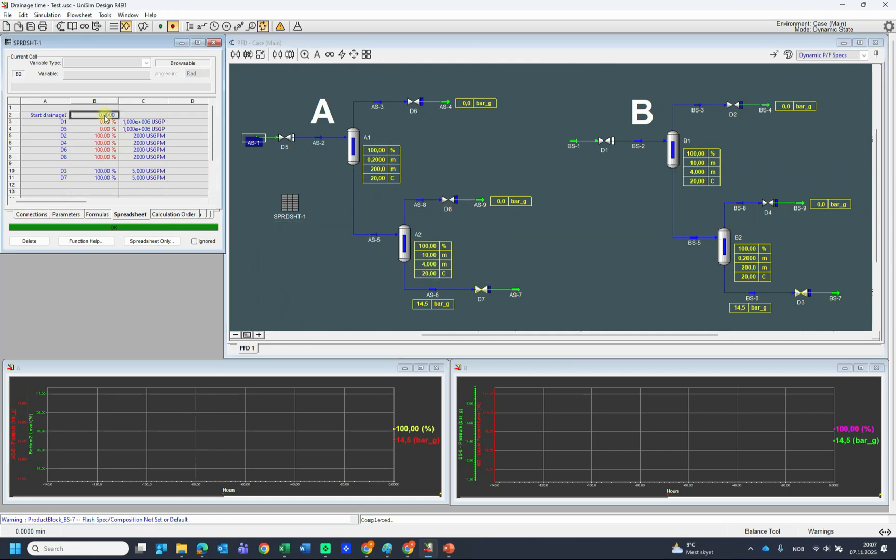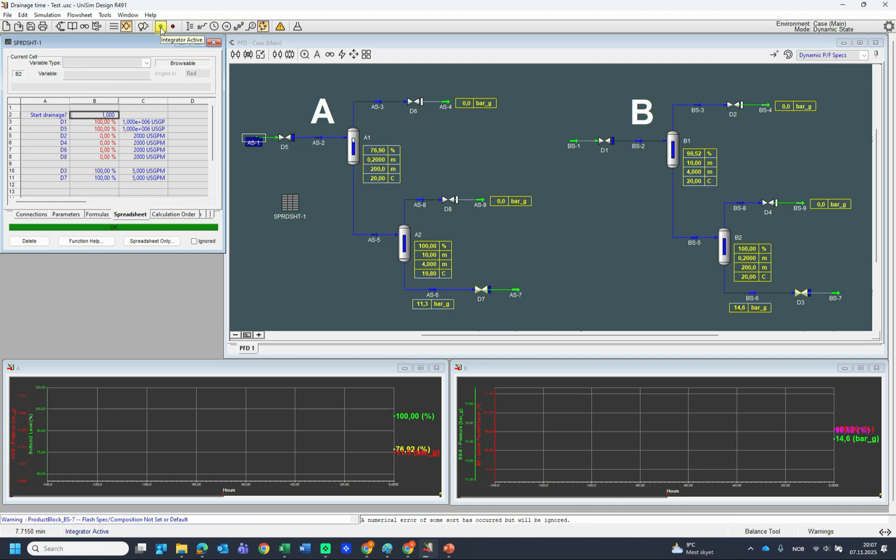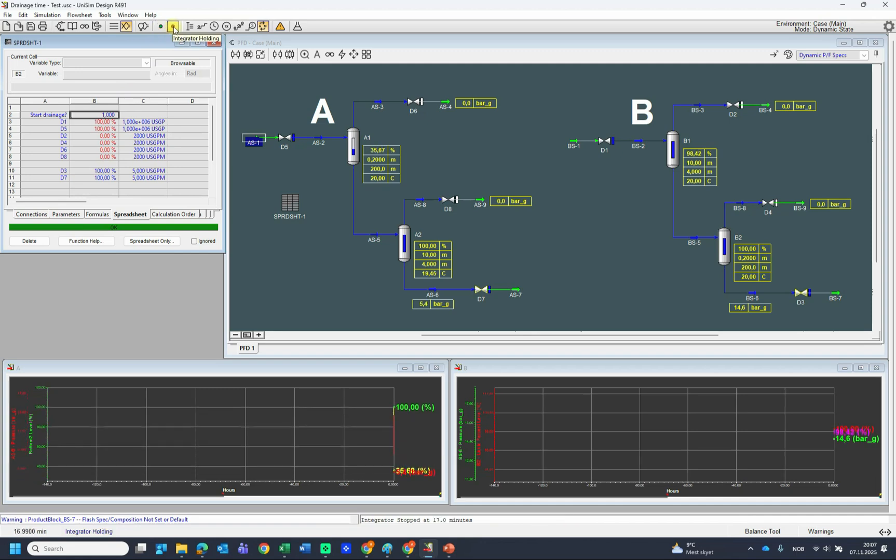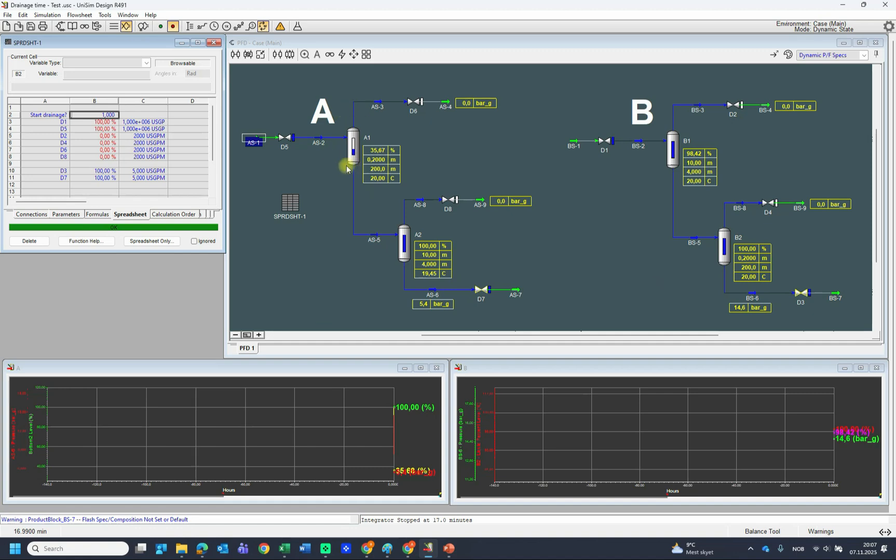So if I start the simulation, let's see what will happen. Let's stop it here and discuss a bit. When I started the simulation, initially the pressure at time zero was 14.5 bar gauge at the inlet of this valve and also this valve. But since for this one, the long pipe with a small diameter which has a very small volume, it drains very quickly.